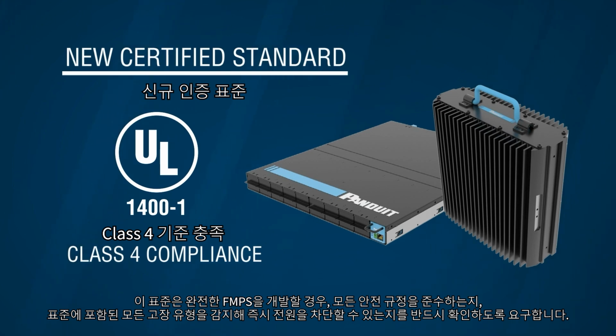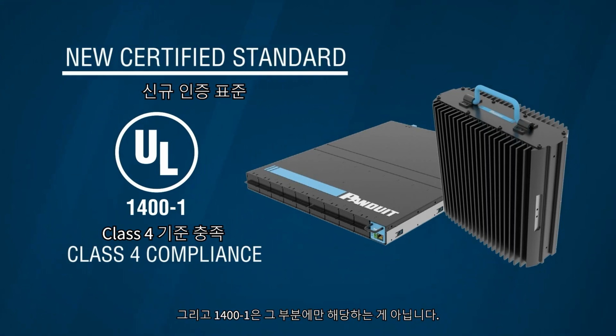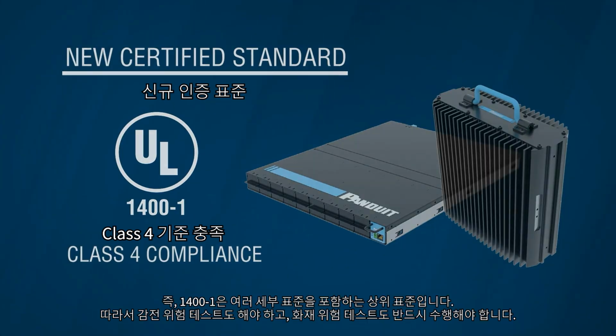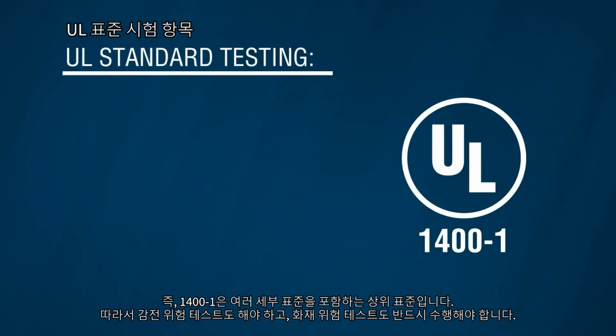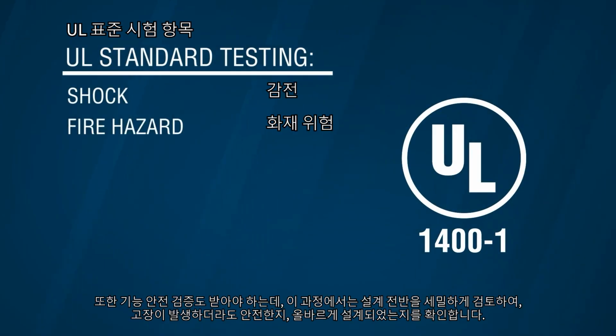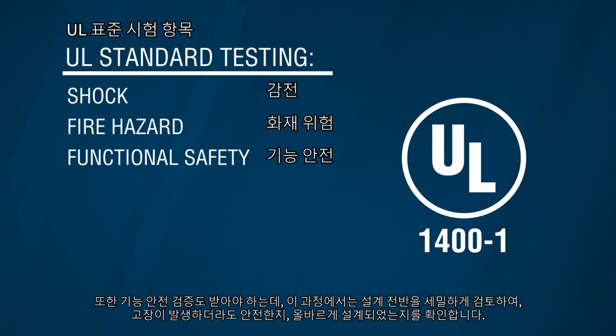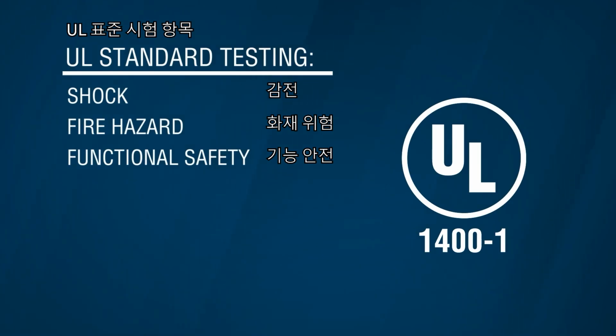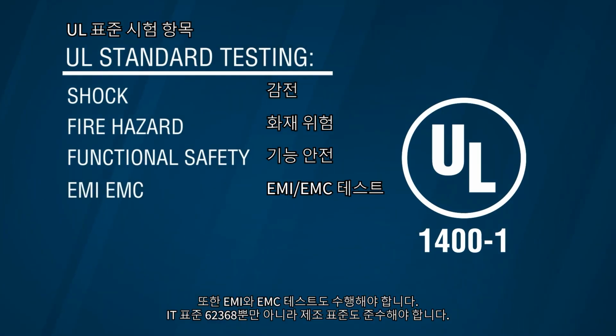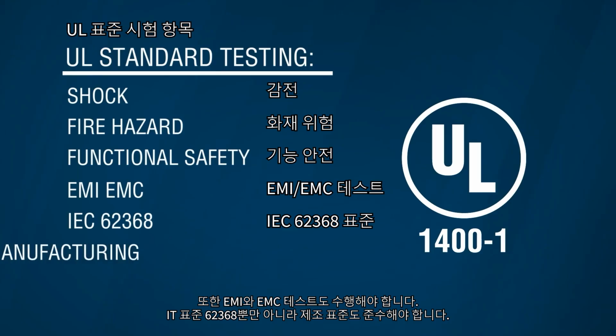It wants to make sure that if you develop a fault managed power system, it adheres to all the safety regulations, or the system can detect all of the faults that are within that standard and turns power off instantly. And 1400-1 is not just that portion of it. It's an umbrella standard that has many others underneath. So you have to do shock testing, you have to do fire hazard testing, you also have to do functional safety, where they look at your design to make sure that it fails safe and is properly designed. They also have EMI, EMC testing. There is adherence to the IT standard 62368, as well as manufacturing standards.